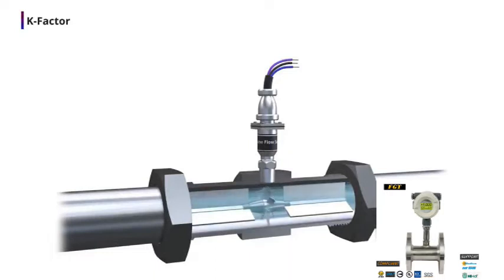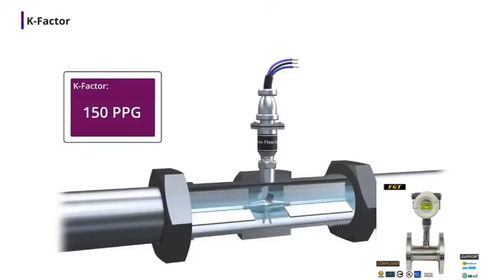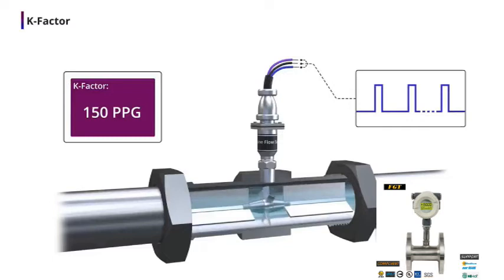When you buy a turbine flow meter, it should arrive with a tag or a calibration certificate declaring its K factor. This K factor is unique to each and every turbine flow meter and is determined by the manufacturer. As we discussed earlier, the turbine flow meter will generate pulses, and the pulse rate depends upon the fluid velocity. The unique K factor declares the number of pulses that will be generated for every unit of product passing through it. K factor will be expressed in terms of the number of pulses produced, such as 150 pulses per gallon.